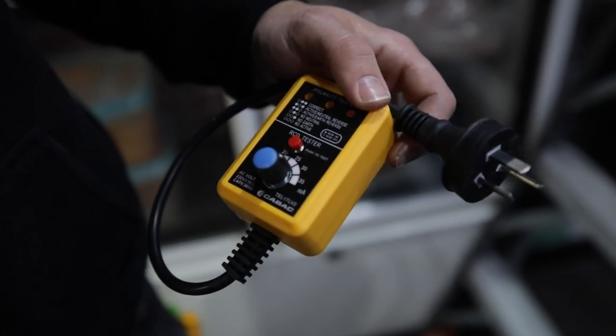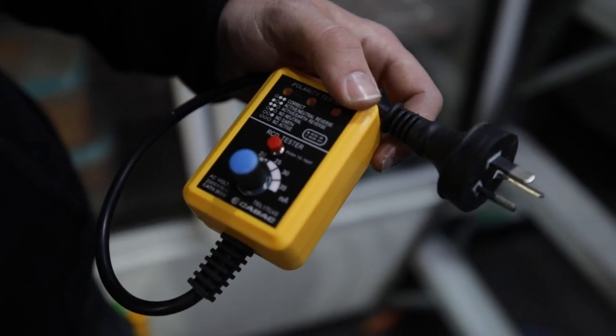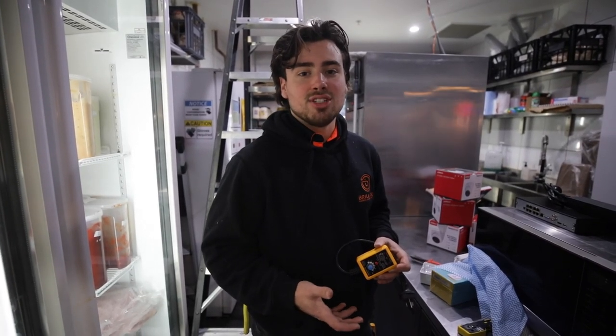This here is the device that Ross used to trip the circuit — it's known as an RCD tester. It tests that a circuit is protected by an RCD by causing it to trip, suggesting that it is functioning correctly. Ross plugged this into the power point he tapped into to get power to the NVR, and from there he knows the circuit is dead and can safely work on it. He's not going to risk any chance of electrocution or danger to himself or others. It's all about making sure we're not getting injured on the job and we're going home at the end of the day.